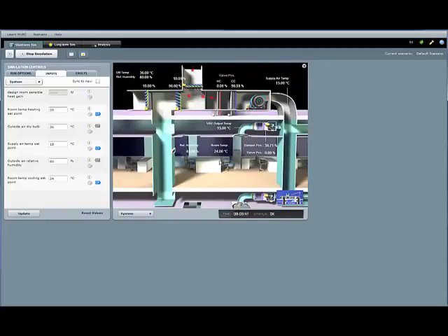We are now going to look at another aspect. We're changing the outside air and adjusting it a bit, and here we see the valve has gone down from 100% to 75%.